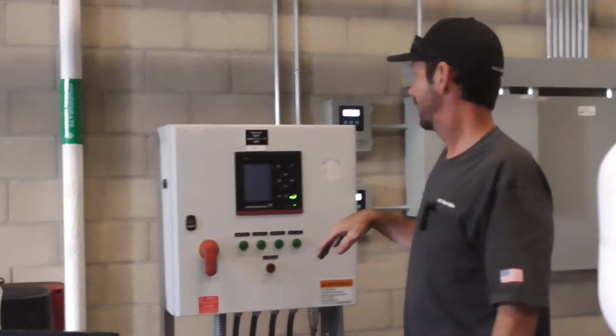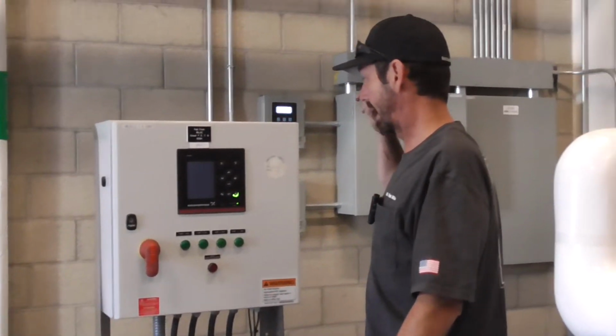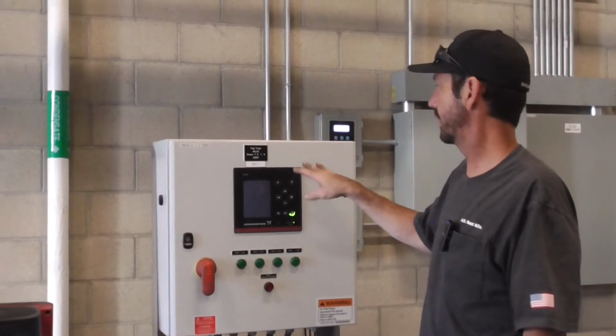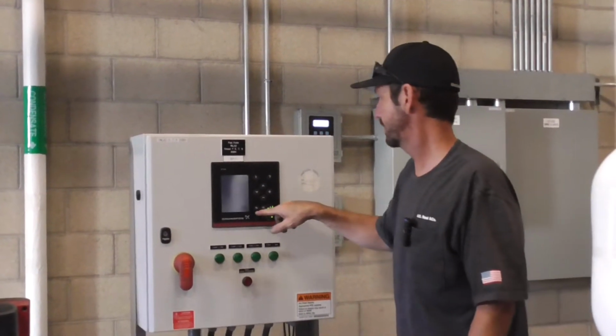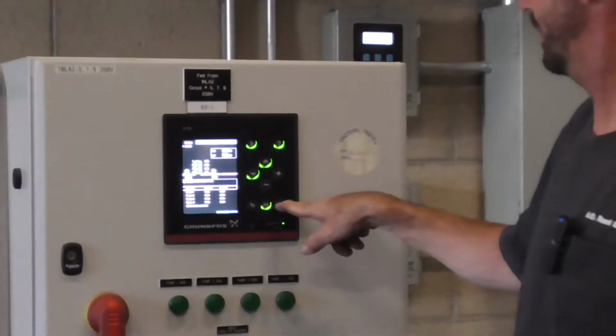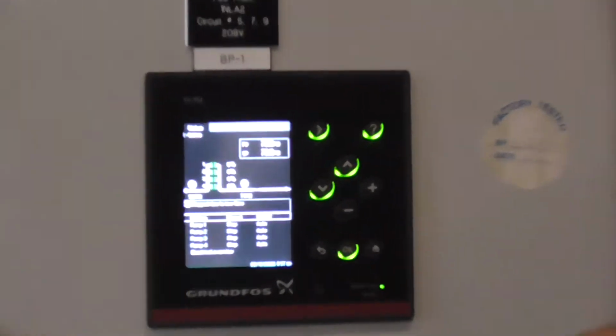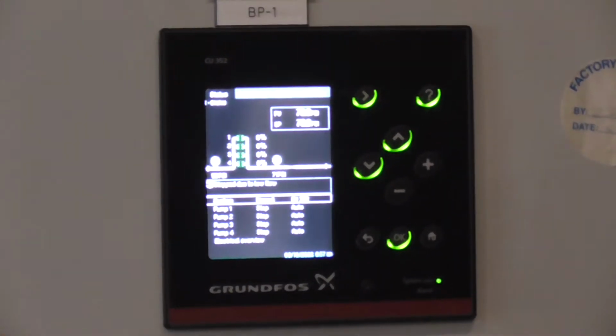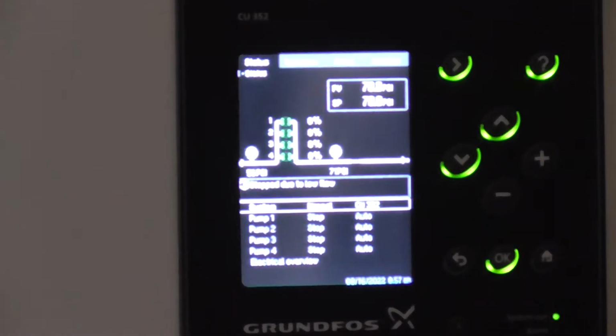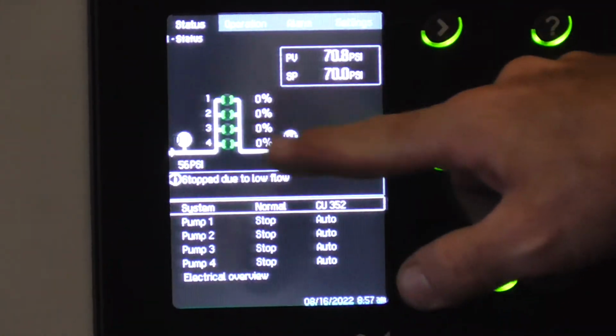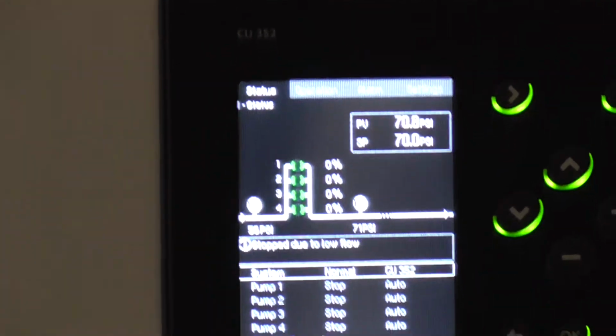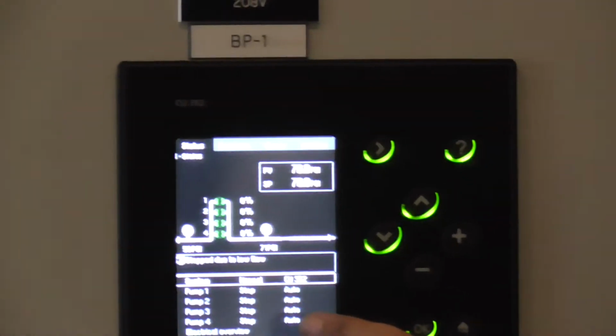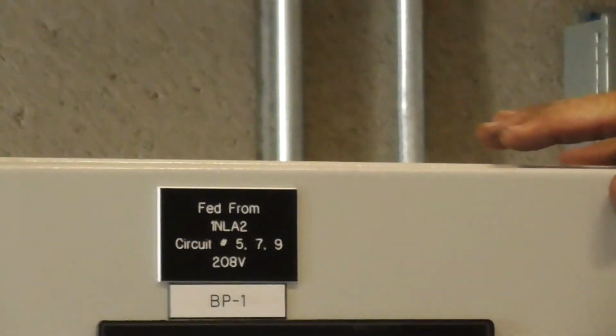So this is a Grundfos unit. Right now the unit is in sleep mode, so to wake it up we can press the home button here. We want to make sure the disconnect, the main disconnect switch right here, is on. We've woken it up, this is our main screen in the status mode. Right now we can see that we're in system normal and all the pumps are stopped, all the pumps are in auto.